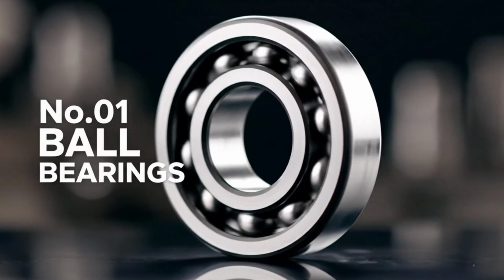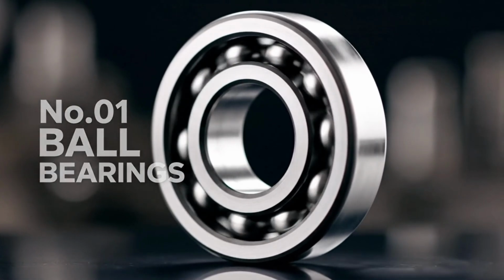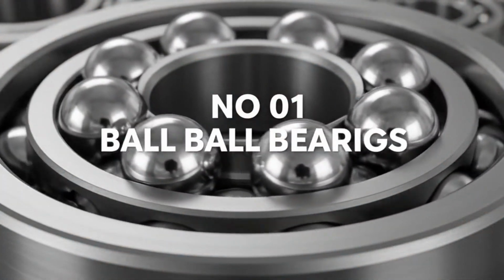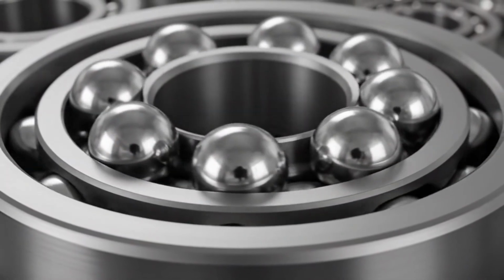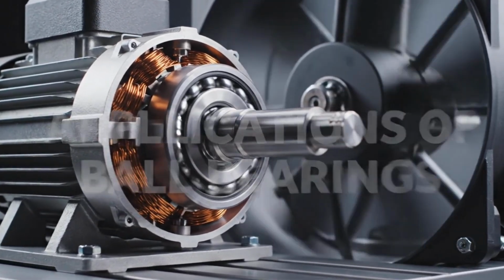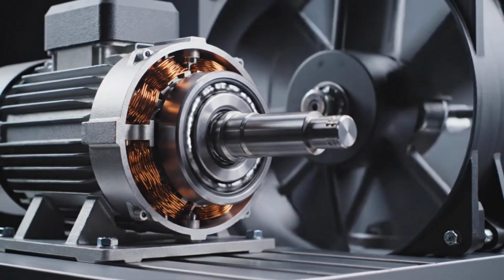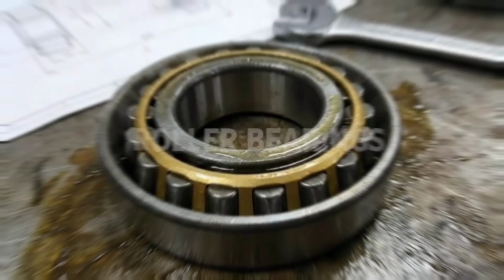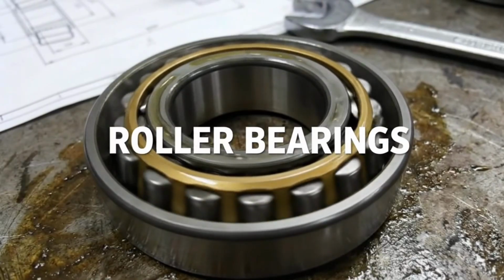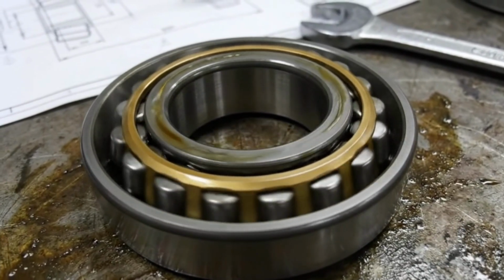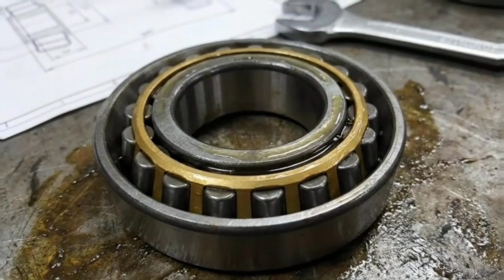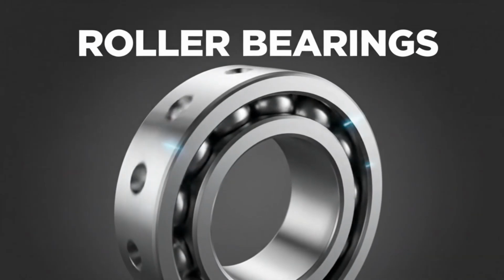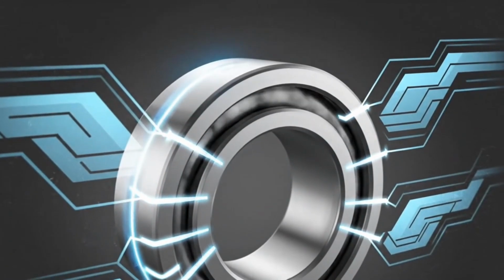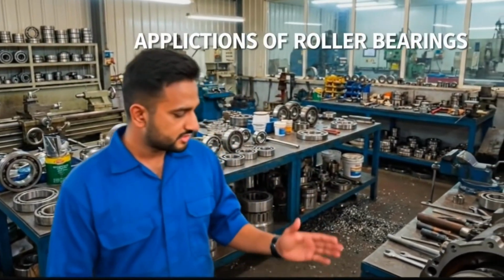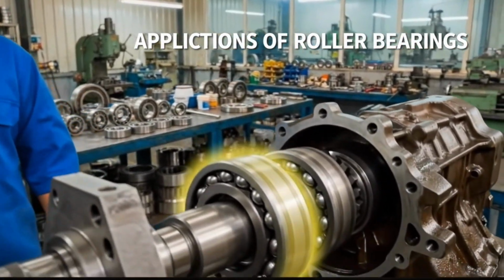Ball bearings use spherical rolling elements and are suitable for high-speed and low to moderate load applications, because the point contact between balls and raceways produces very low friction. They are commonly used in electric motors, fans, pumps, and precision instruments. Roller bearings use cylindrical rolling elements to support heavier loads than ball bearings, due to line contact between rollers and raceways, which distributes load more evenly. These bearings are used in gearboxes, conveyors, crushers, and heavy machinery.